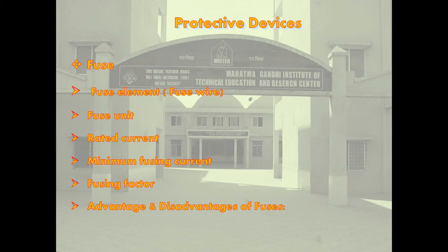Materials commonly used for fuse elements are tin, lead, silver, zinc, copper, aluminum, etc. In general, no material possesses all the desirable characteristics. Working experience with fuses has proved that the most suitable material for the fuse element is a low melting point material such as tin, lead, or zinc. A low melting point material has high specific resistance.